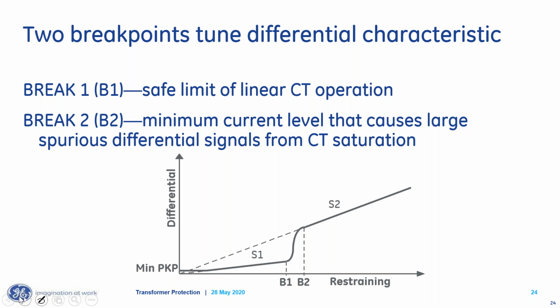Upper slope. The upper slope is where we could have a lot of CT saturation. One of the things we could do is model our CTs. We could use the PSRC tool that models CTs, and say, okay, this set of CTs is going to perform perfectly, so that looks like 10,000 amps, whatever it looks like. And then we could model performance and say, okay, this CT saturates at, it looks like, 2,000 amps. That means I need a slope of 80%. That's one way you could do that.